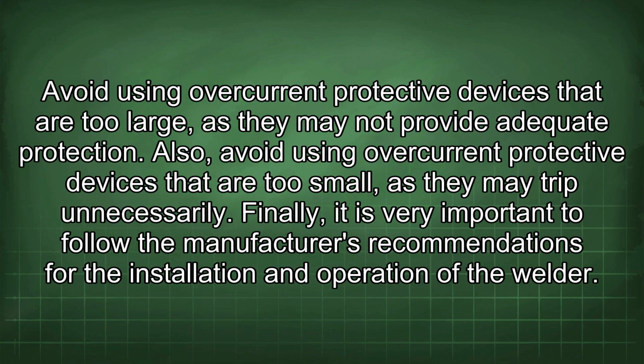Avoid using overcurrent protective devices that are too large, as they may not provide adequate protection. Also, avoid using overcurrent protective devices that are too small, as they may trip unnecessarily.